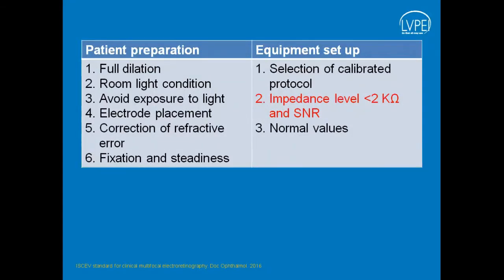As we have discussed in the previous talk on full-field electroretinogram, here also you should keep in mind the signal to noise ratio as well as the impedance level, which is highlighted here. Simultaneously, the patient should avoid any intense light test, like fundoscopy, FFA, OCT. If it is done, then the patient should be adapted in natural light for the next half an hour or 1 hour approximately before we process the multifocal ERG test.